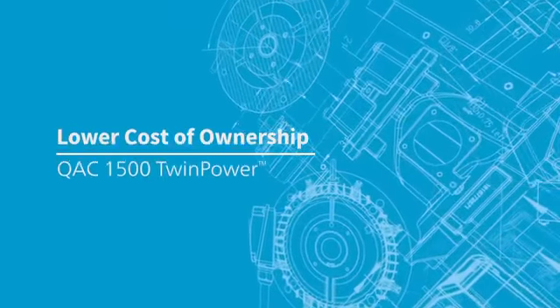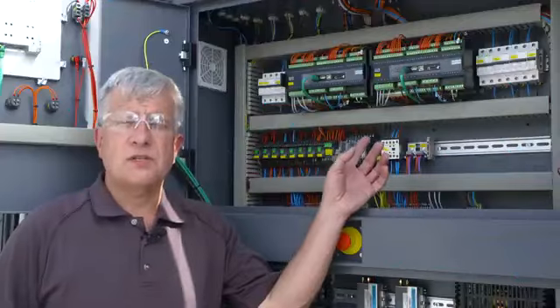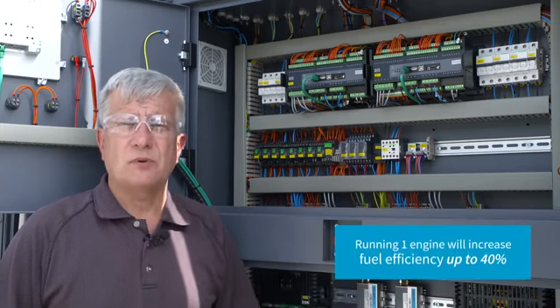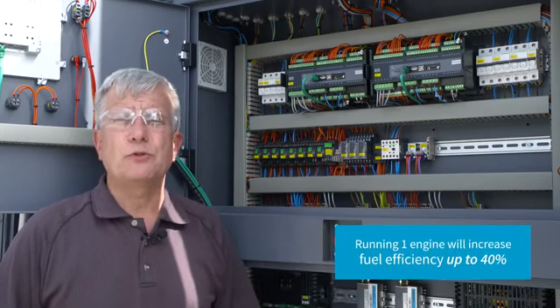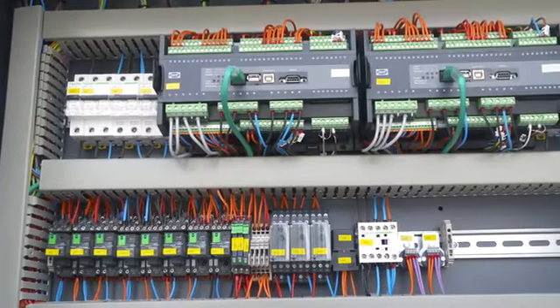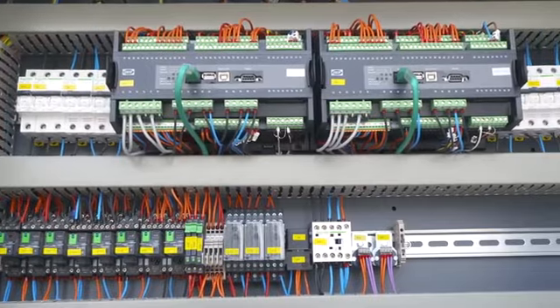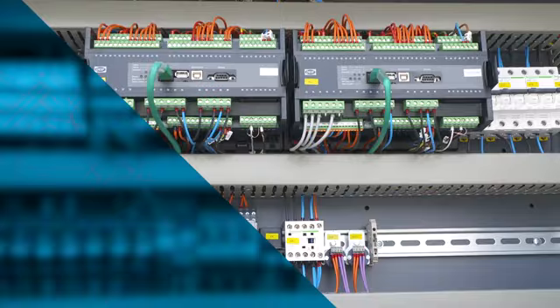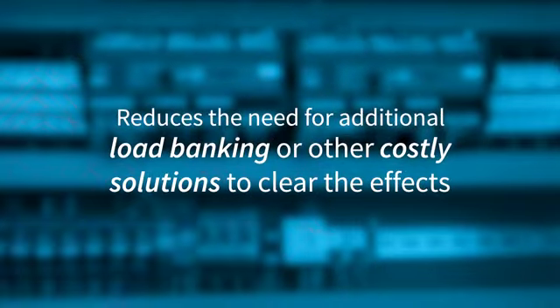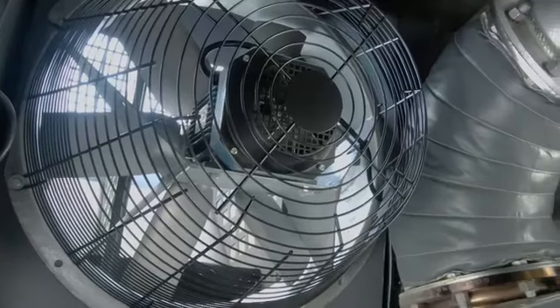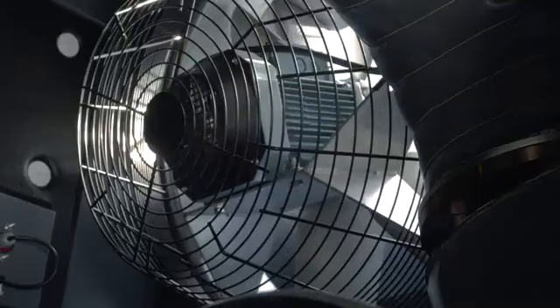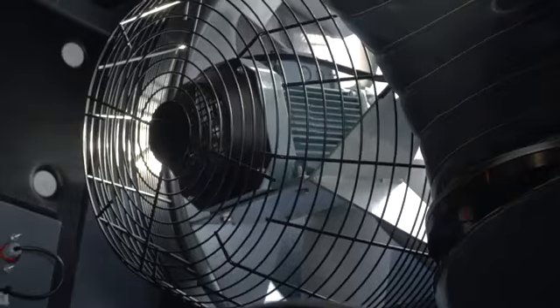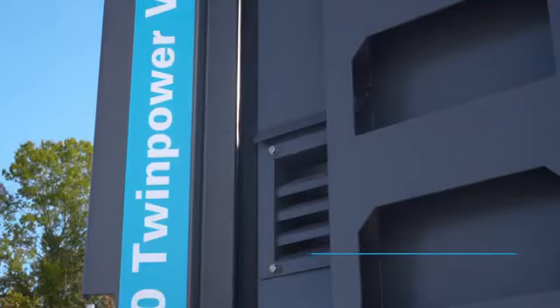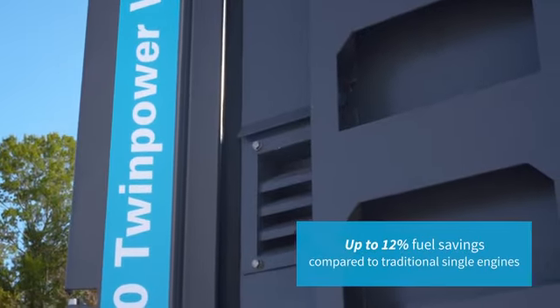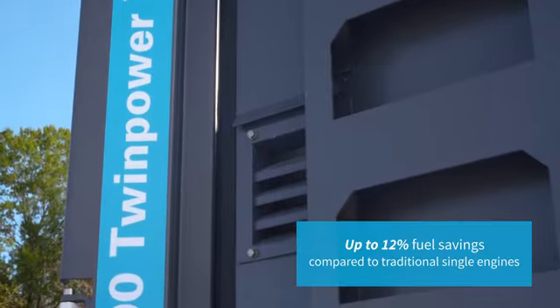Lower cost of ownership. The PMS system will run one engine when possible, increasing fuel efficiency up to 40%. This reduces the effects of low loads, providing a longer life for the engine, reducing the need of additional load banking or other costly solutions needed to clear out the effects. Additionally, the electro fans will adapt their speed to the working conditions, optimizing energy consumption and providing up to 12% fuel savings compared to traditional direct flow cooling systems.